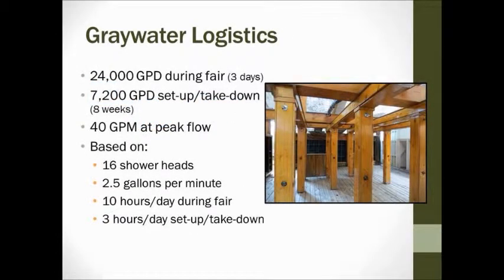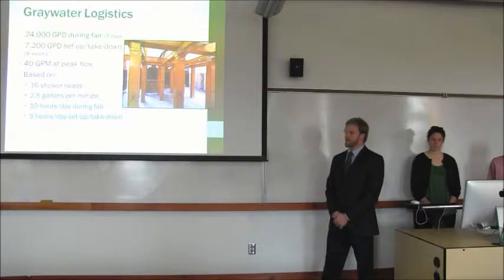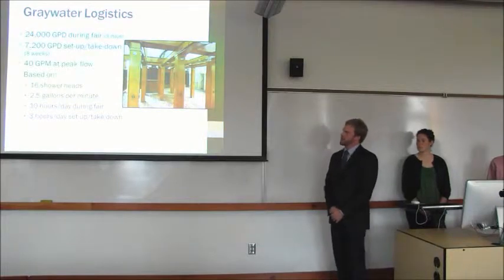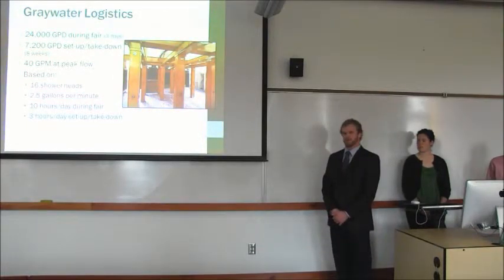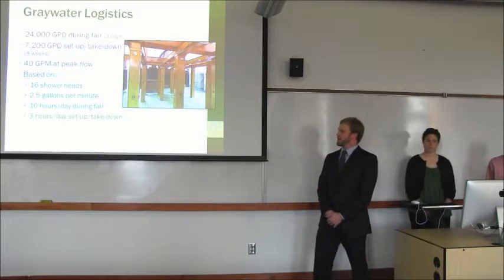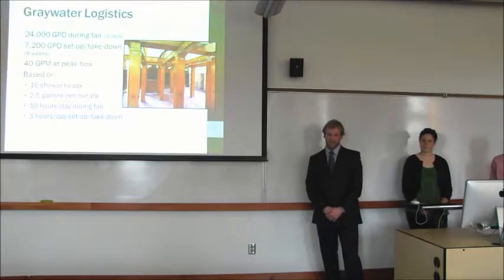Here's a quick look at the different flow numbers. We have about 24,000 gallons per day during the fair, which is three days long, and about 7,200 gallons per day during setup and takedown, which is about eight weeks during the summer. Our peak flow is 40 gallons per minute, found by taking the 16 showerheads and multiplying by 2.5 gallons per minute — the max flow rate per the Energy Policy Act of 1992. We assumed about 10 hours per day during the fair: four hours in the morning, four hours at night, and about two hours midday. During setup and takedown, we assumed three hours per day, as told to us by one of the fair elders.